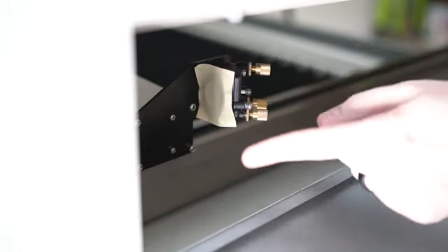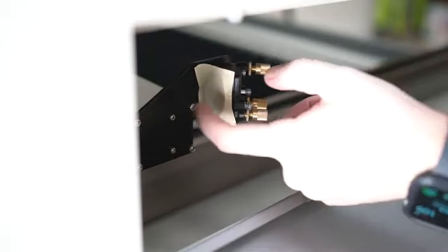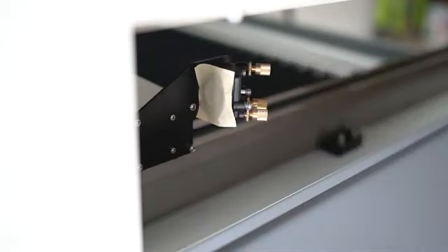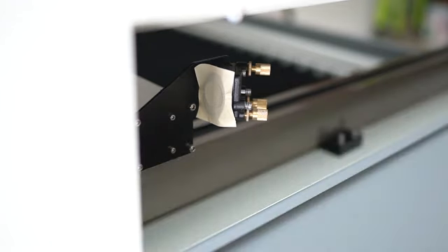So as it leaves the laser tube, it bounces off that mirror. Is that mirror in a position to get us directly in the center of this housing? Let me power everything up and I will pulse the laser real quick. If you get a machine protected error when you go to pulse, it's because the top is open and it's trying to protect you basically. So I close the top. Now let's try and pulse here.